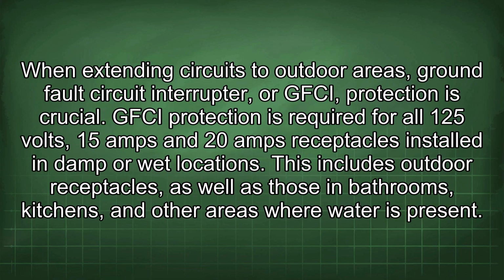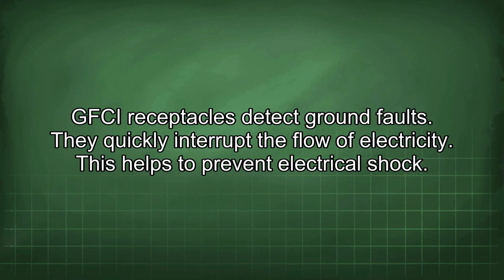When extending circuits to outdoor areas, ground fault circuit interrupter, or GFCI, protection is crucial. GFCI protection is required for all 125 volts, 15 amps and 20 amps receptacles installed in damp or wet locations. This includes outdoor receptacles, as well as those in bathrooms, kitchens, and other areas where water is present. GFCI receptacles detect ground faults. They quickly interrupt the flow of electricity. This helps to prevent electrical shock.